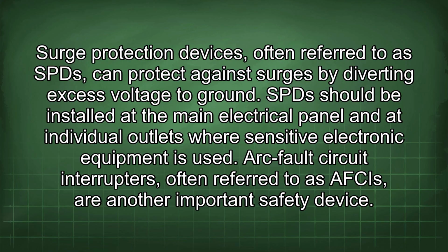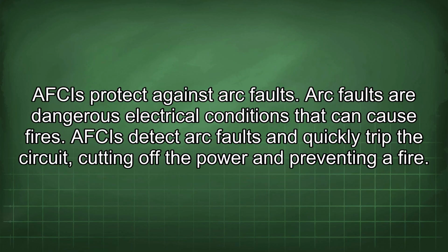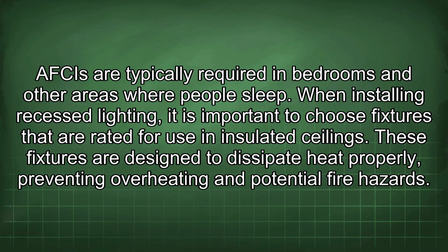Arc fault circuit interrupters, often referred to as AFCIs, are another important safety device. AFCIs protect against arc faults. Arc faults are dangerous electrical conditions that can cause fires. AFCIs detect arc faults and quickly trip the circuit, cutting off the power and preventing a fire. AFCIs are typically required in bedrooms and other areas where people sleep.